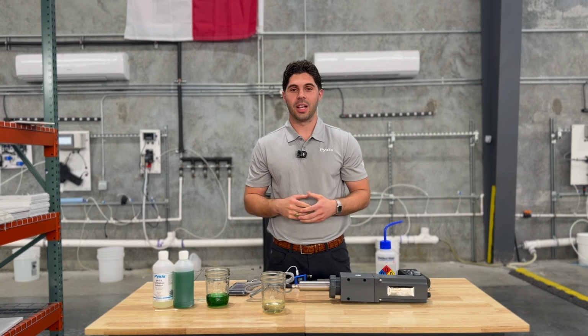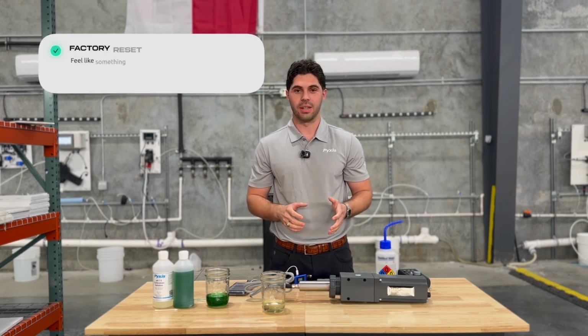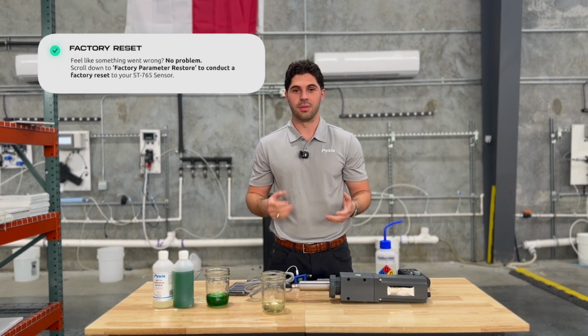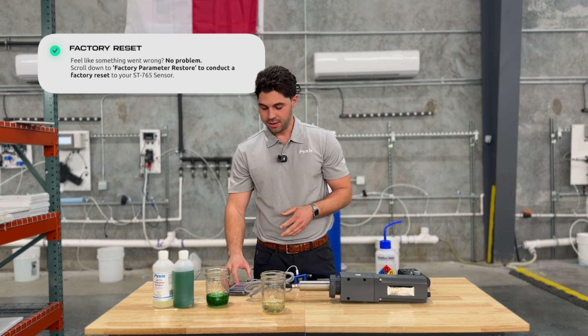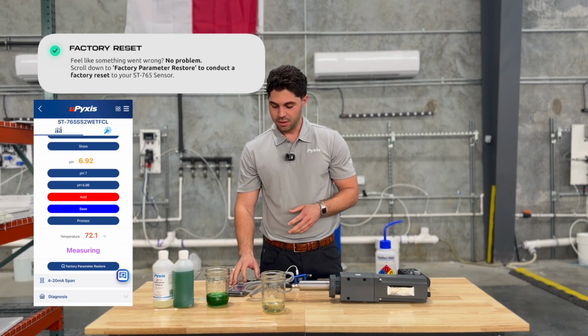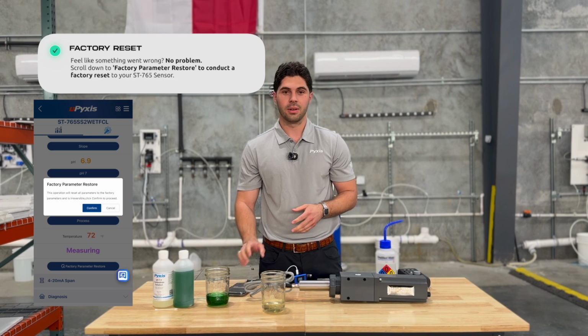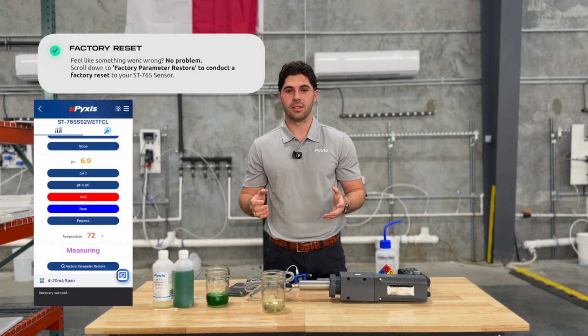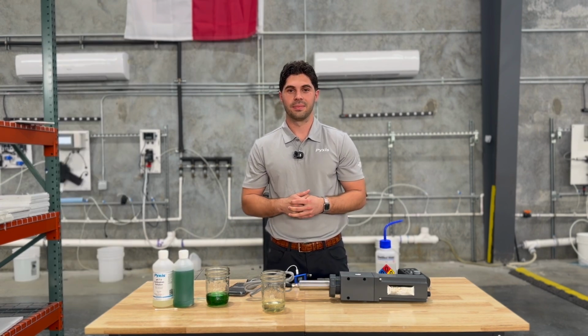If for some reason your calibration is way off or you're still getting sporadic readings, you can perform a factory reset. This can be found under the pH section. You're going to want to click Factory Parameter Restore and confirm. This will return the sensor to its factory settings.